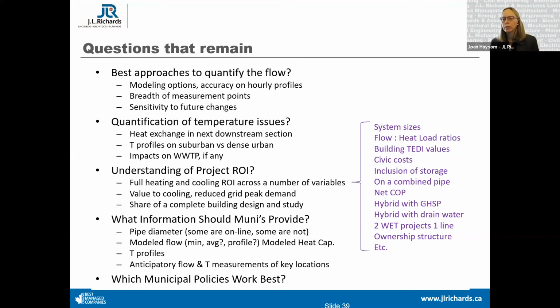Yeah, there's two factors going on. The actual energy transfer efficiency is very high in this system compared to, say, a cooling tower, and some of the maintenance may be lower as well. You're also taking basically the same capital investment and using it through both seasons. Whereas the old-fashioned approach is a natural gas boiler system and a separate set of cooling towers, so you have to factor in both of those business-as-usual costs against the single heat pump energy transfer system. The overall package works really well.